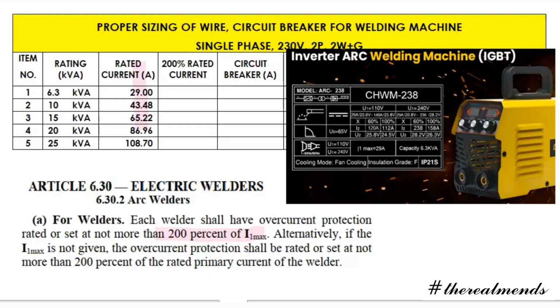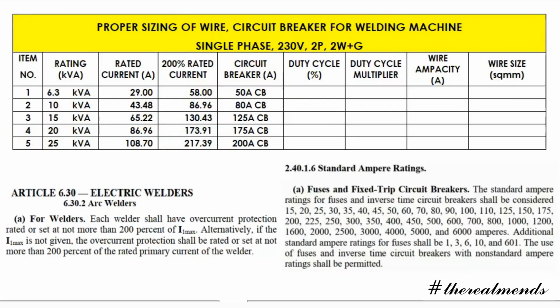So therefore, this rated current, let's multiply it by 2 or 200%. So we have 58, and then just drag this down. Okay, so we have 86.96 for 10 kVA, 130 for 15 kVA, 173.91 for 20 kVA, and so on. After that, we can have a rating of the circuit breaker.